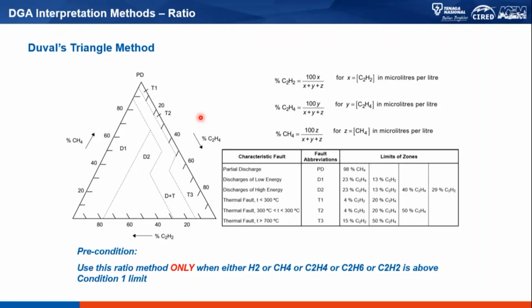It only uses 3 main combustible gases: methane, ethylene, and acetylene. This is how it is calculated to get the percentage of all 3 gases, and once the calculation is done, we can plot where the point is, and that will tell us whether the fault is partial discharge, discharge of low energy, and so on and so forth.